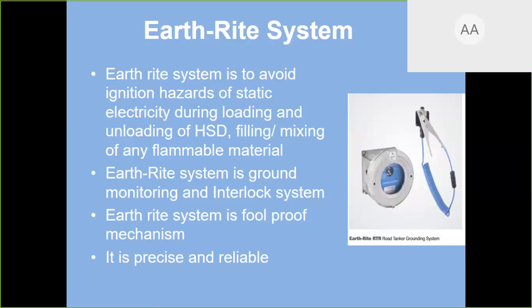It is very precise and reliable equipment. Very small equipment which can be installed in the transfer line, filling line, loading line, and mostly when the HSD is transferred from the tanker to your tank, and there is a pump which will transfer, and if the Earth Ride system is connected, the pump will not start until it ensures the earthing continuity. So this Earth Ride system will make sure that your earthing is correct and there is no chance of static electricity, and there is no ignition due to static electricity, and there is no fire in HSD due to ignition which is due to static. This is my third system, which is known as the Earth Ride system.